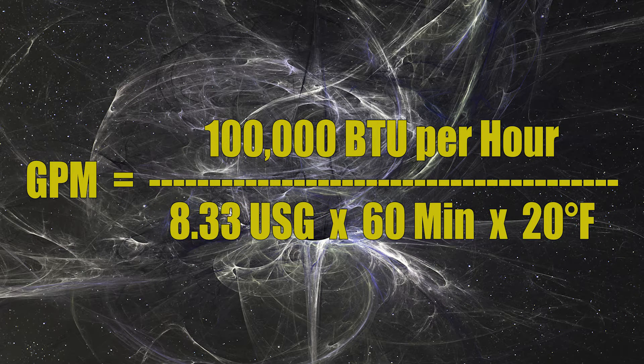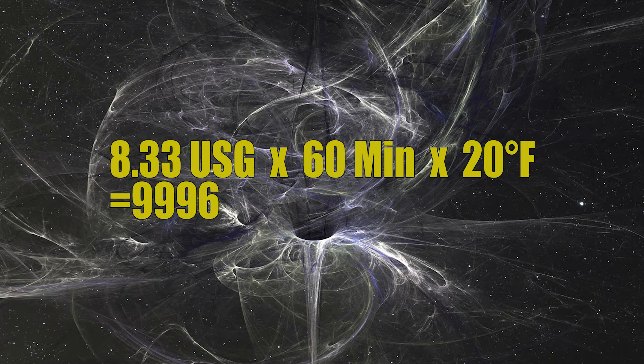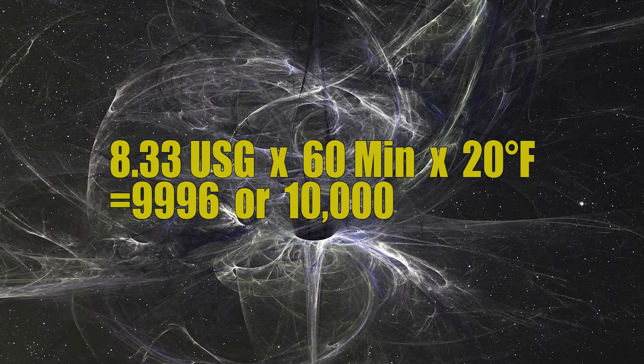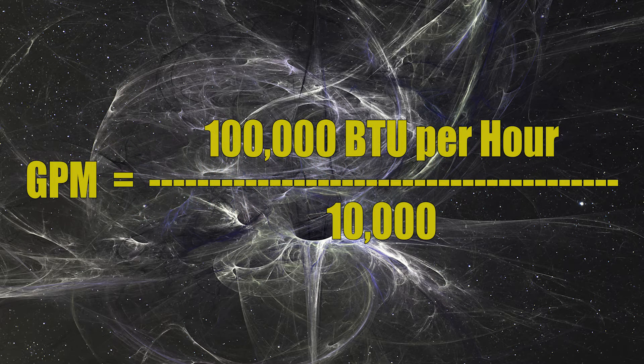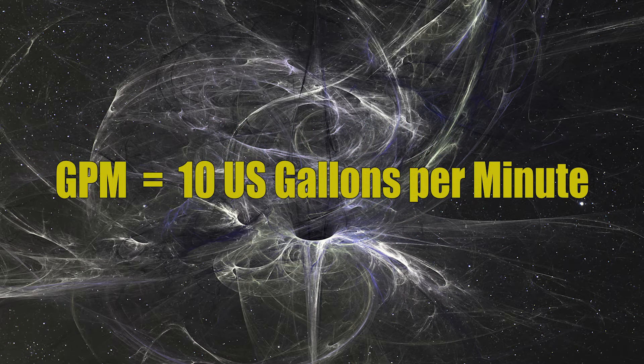The smartest way to do this math is to do all the multiplication on the bottom line first. So I have 8.33 times 60 times my delta T of 20 degrees Fahrenheit. When I plug that into my calculator I get 9,996 — which is so close to 10,000 that we just round it off to 10,000. Then I take my BTU load of 100,000 and divide it by 10,000, and I get a GPM of 10.